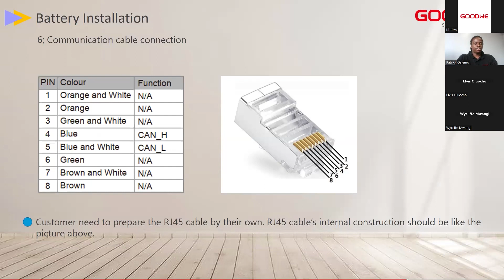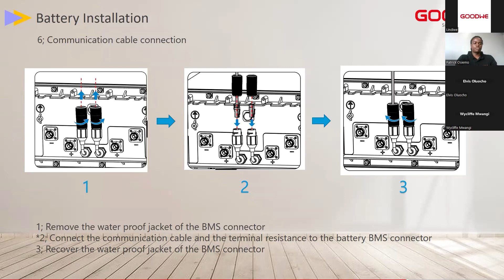Communication-wise it's easy, using the CAN protocol with RJ45 connectors in a daisy chain loop. You connect the BMS communication from the inverter to the battery PCU, and since it's a CAN protocol, the remaining terminal needs a terminating resistor, which comes as an extra accessory with the battery—no need to purchase it separately. Once connected, you're done with the communication cable termination in a simple plug-and-play scenario.